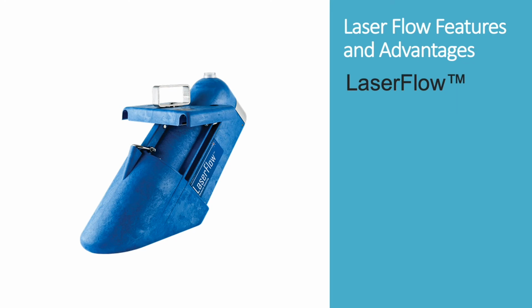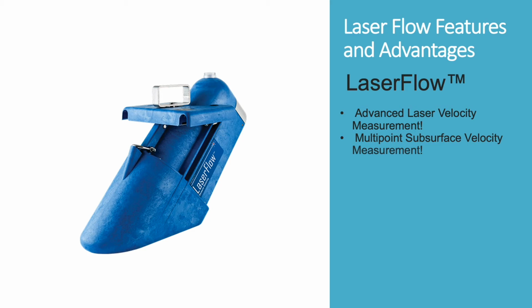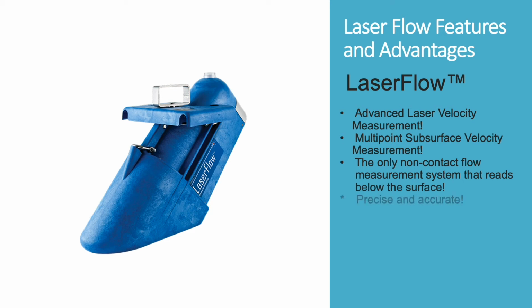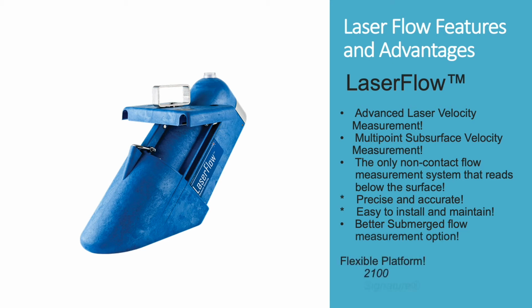Laser flow advantages are quite substantial. The advanced laser velocity measurement, multi-point subsurface velocity measurement, 15 different points, 3 different levels. It is the only non-contact flow measurement system that reads below the surface. It is extremely precise and accurate. It's easy to install and maintain, and we can even do submerged flow measurement as an option if you're involved in flow measurement in a line where you're accessing through a manhole and occasionally that manhole becomes surcharged. Very flexible platform with the 2100 series and the signature platforms.